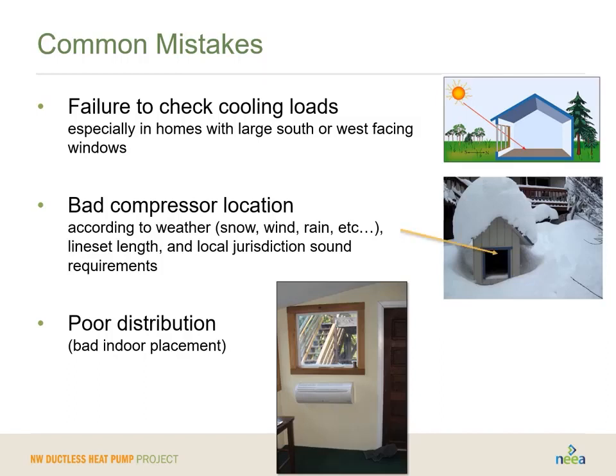You want to make sure that it's at least covered. Now, obviously, I'm not talking about putting the compressor in the doghouse, but what we mean by that is making sure that it's going to be protected from the elements. We've actually seen outdoor units buried under snowdrifts. That is not going to work very well. You need to have clear space around it. You need to have it not be in a high wind zone and not in a high snow zone.